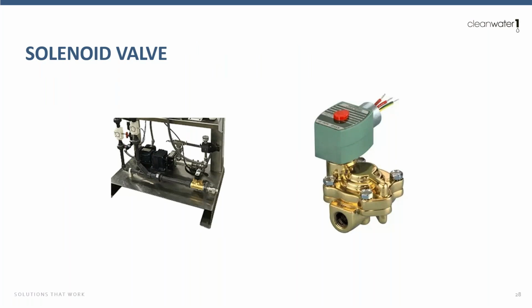So making sure that we have the correct water requirements for the system is important. And when we do have a certain amount of solids in the water, it's a good idea to start considering some sort of strainer upstream to collect any biological growth in the lines or any solids that are in the water itself to help this solenoid valve operate efficiently.